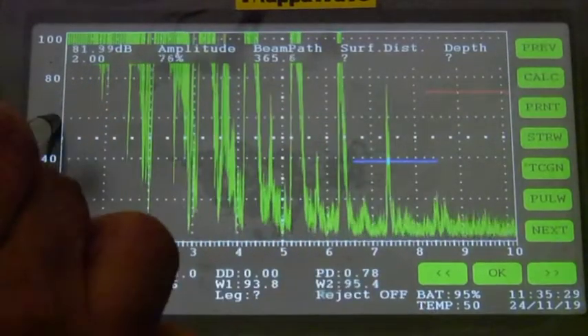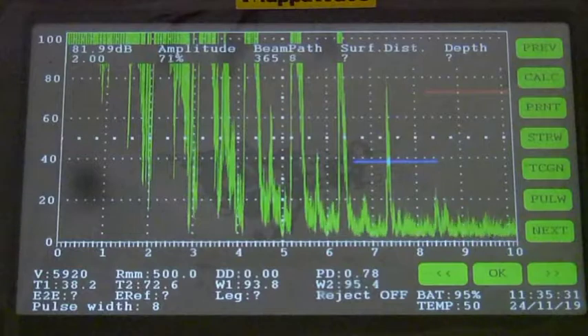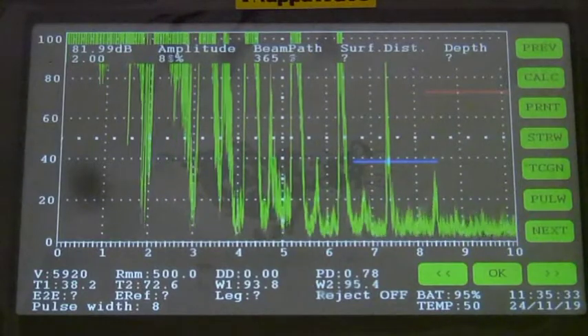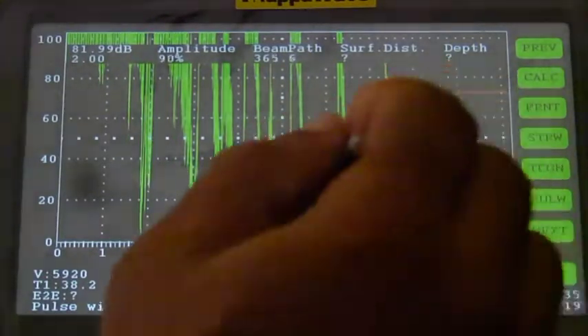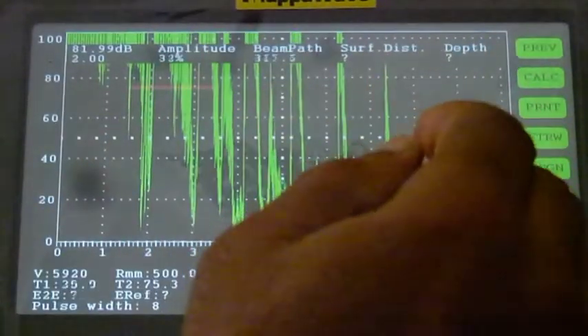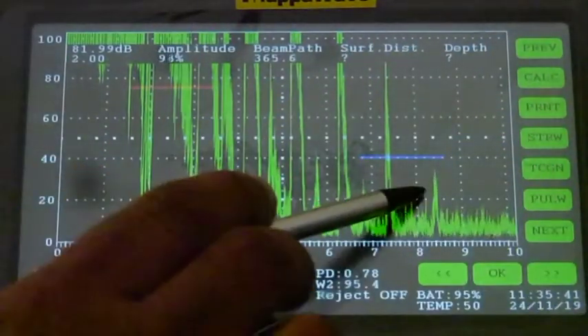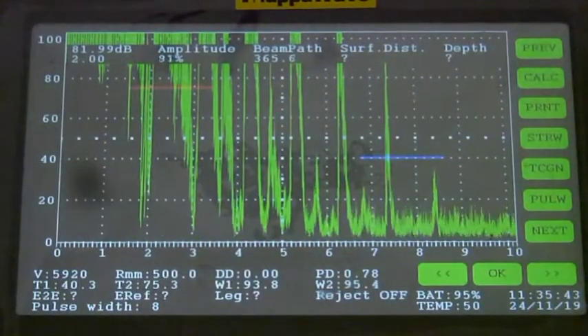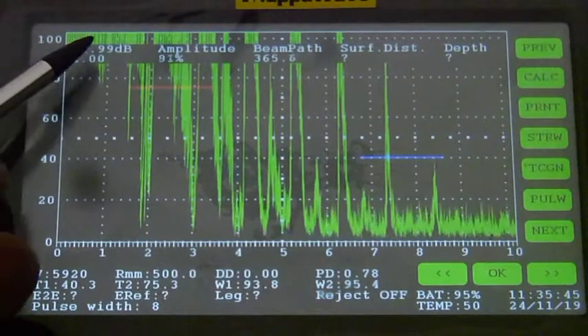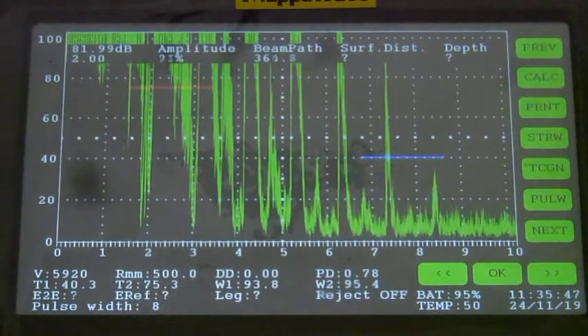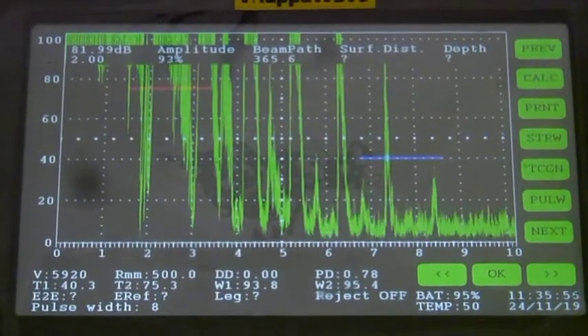That's about 77-80% in height. And the 8th backward echo can be seen. That's nearly about 35%. You can also look at the noise level, which is fairly low. It is about 81 or 82 dB now. This makes this instrument very usable for casting industries, where high penetrative power may be required.